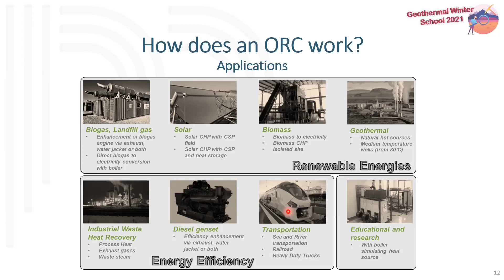ORC used at biogas landfill for both jacket water and exhaust heat recovery. For the genset, you will burn some methane, some biogas. You will produce exhaust gas. We'll have, on the hot loop, circulation of water.